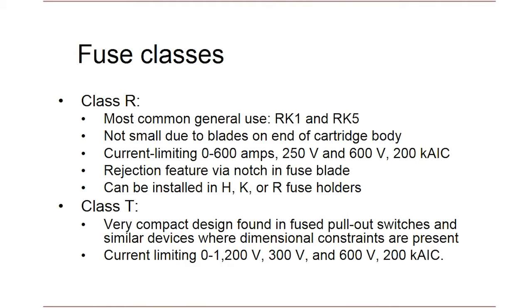Class R fuses are found in a wide variety of applications up to 600 amps. The two types you'll typically encounter are RK1s and RK5s, which we'll discuss shortly. Class T fuses are typically available in ampacities up to 1200 amps. They are dimensionally much smaller than other classes, are typically very fast acting with a high degree of current limitation, though not as common. You might find them where their small size is an advantage, such as pull-out fuse switches or meter sockets.